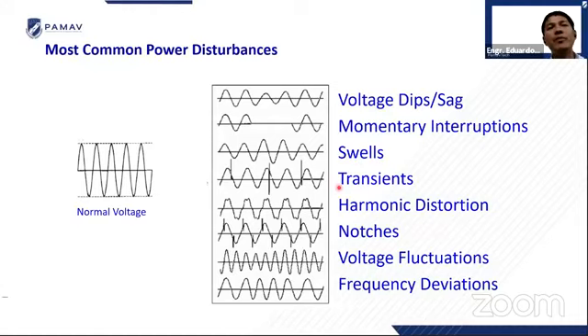And we also call it transient. Transient, usually we encounter it in a distribution system, where you have an overhead line and suddenly a branch of a tree biglang dumikit, or touches the line, and you have some transient. Or sometimes when we have a power transformer or generator that you have started, you have transient, okay? And those transients have a very small time.